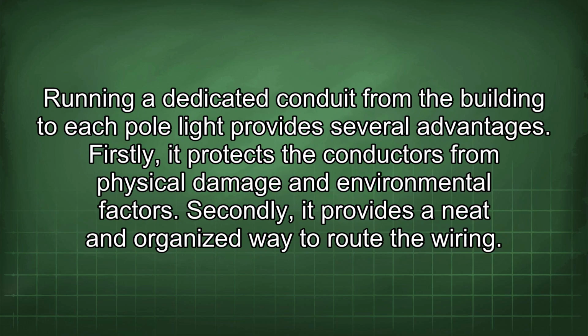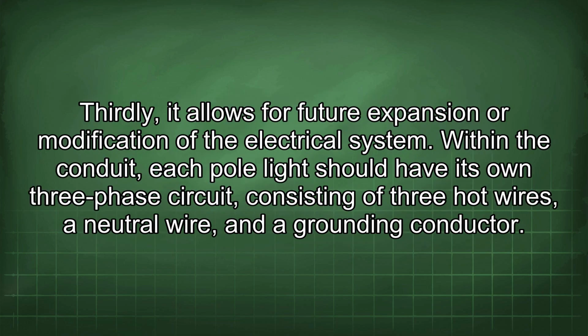Running a dedicated conduit from the building to each pole light provides several advantages. Firstly, it protects the conductors from physical damage and environmental factors. Secondly, it provides a neat and organized way to route the wiring. Thirdly, it allows for future expansion or modification of the electrical system. Within the conduit, each pole light should have its own three-phase circuit consisting of 3 hot wires, a neutral wire, and a grounding conductor.